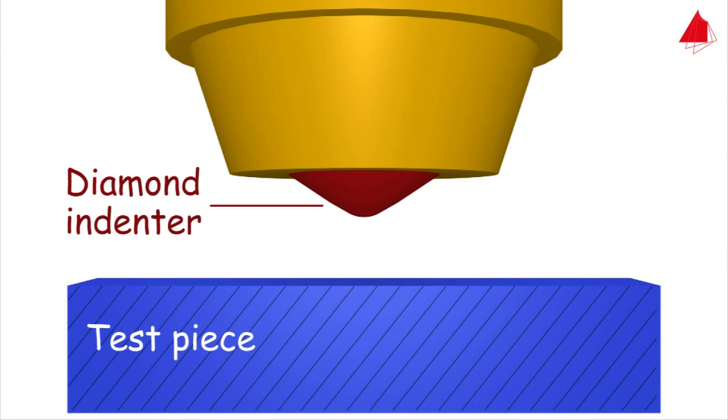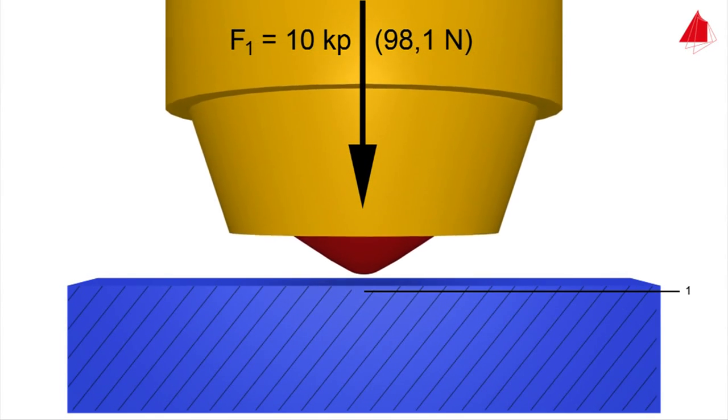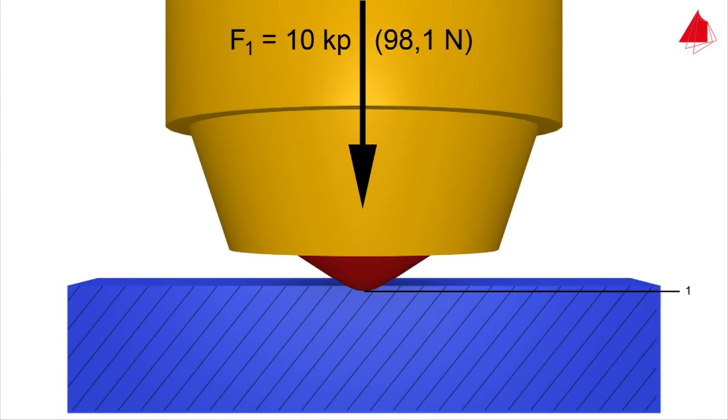In step 1, the diamond cone is pressed onto the test piece surface with a minor force of 10 kiloponds. The depth of indentation under this preliminary load is the reference point.